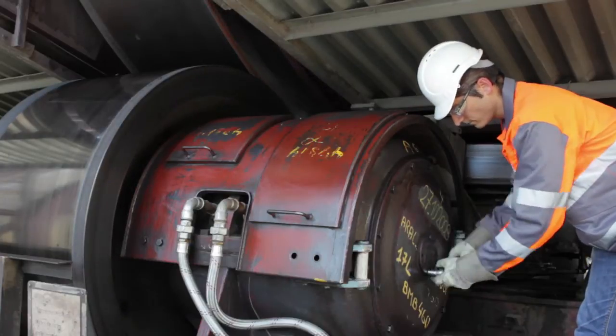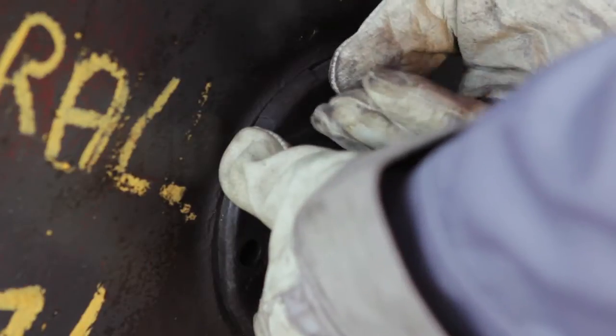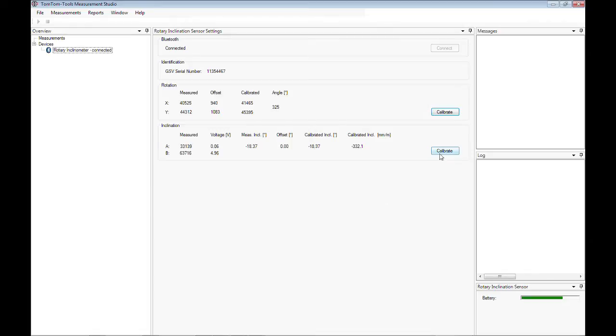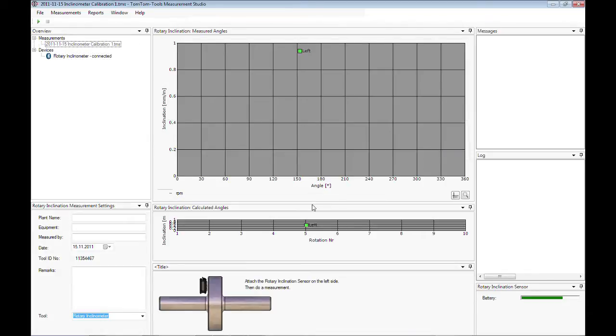In order to perform the measurements, the roller shaft has to be accessed. When opening the cover, ensure to use proper tools and prevent any contamination of the bearing. Now the inclination sensor, which is the main sensor, has to be calibrated on a rotating part.